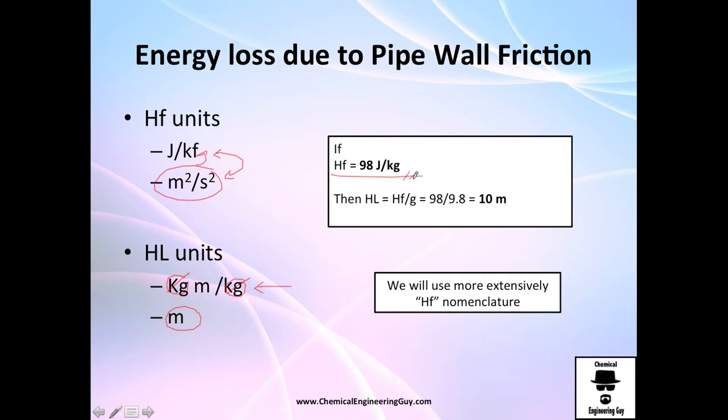So for example, if I were to tell you I got 98 joules per kilogram, then if you wanted to show me how many meters is that, you will need to divide HF by gravity. So 98 divided by 9.8 will give you ten meters. So this means essentially that these ten meters, well you just lose them, so you need to get the tank ten meters below in order to satisfy this friction.